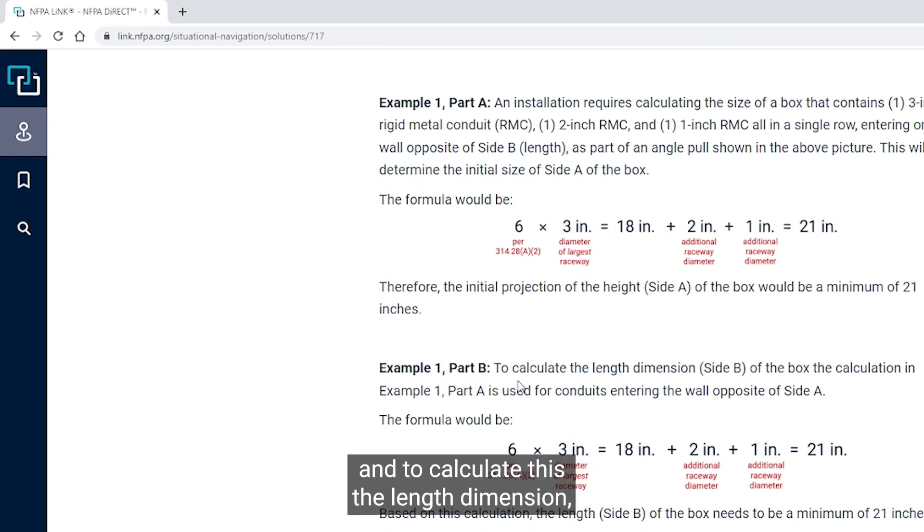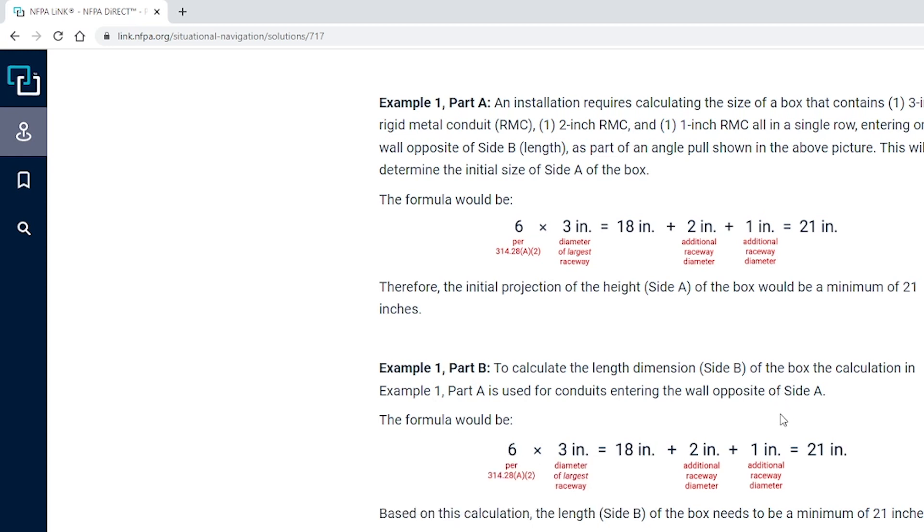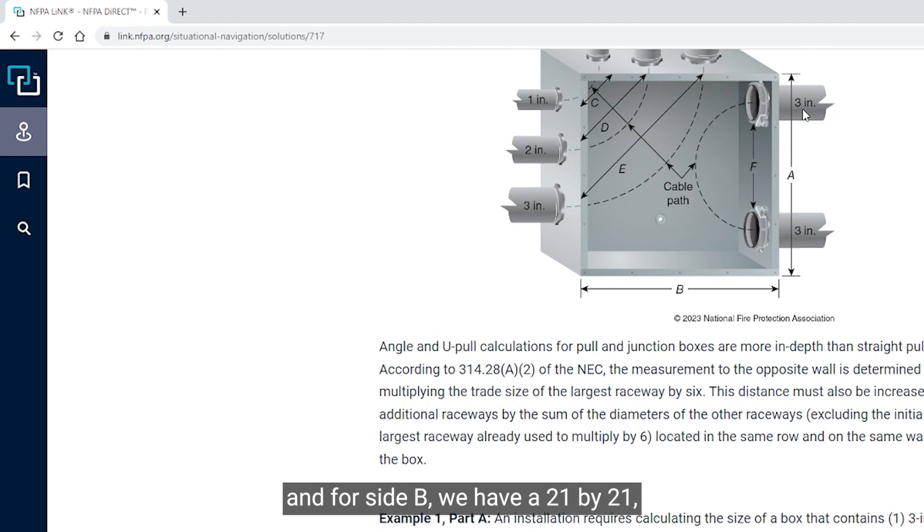This will be the formula: 6 times 3 equals 18, and then we add the other two raceways, which would be 3 additional inches, would give us a 21-inch box. So the installation of this box would be currently the projected side would be 21 inches for side A. Now we need to calculate for side B, which would involve these. We're going to go to Example 1, Part B.